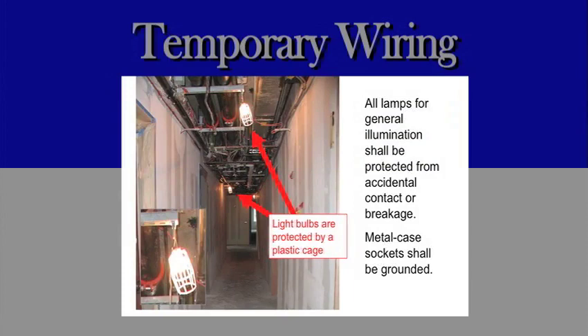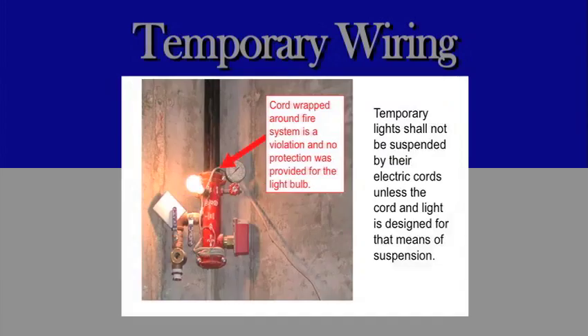Temporary wiring. Light bulbs are protected by a plastic cage. All lamps for general illumination shall be protected from accidental contact or breakage. Metal case sockets shall be grounded. Temporary lights shall not be supported by their electrical cords unless the cord and light are designed for that means of suspension. Cord wrapped around a fire system is a violation, and no protection was provided for the light bulb.